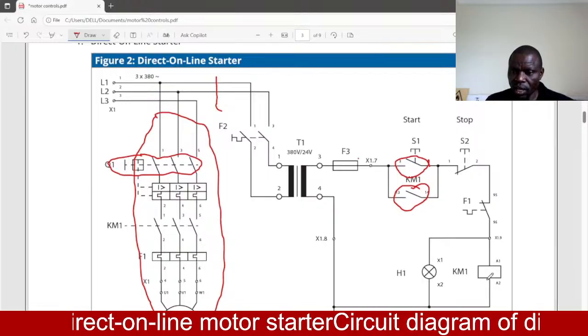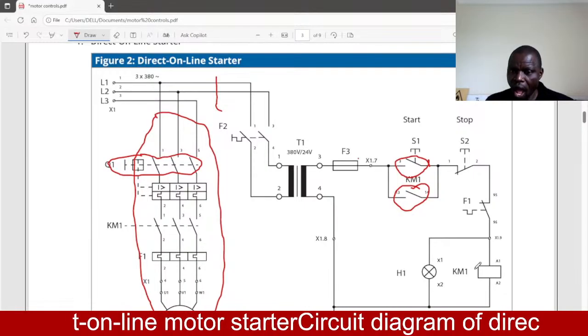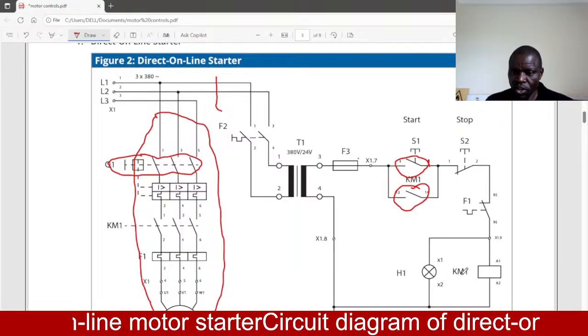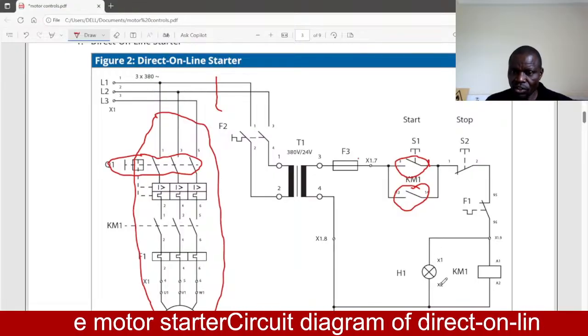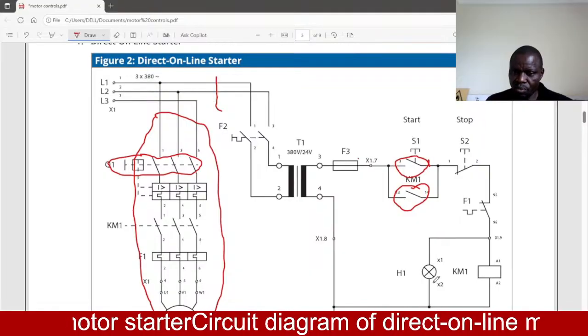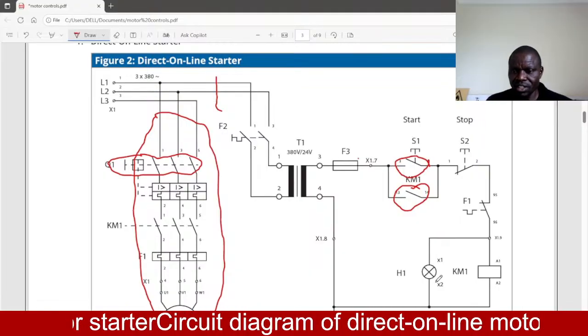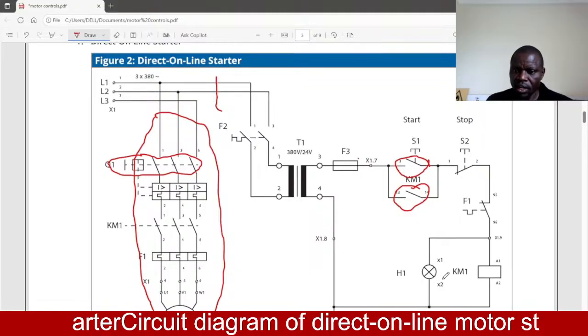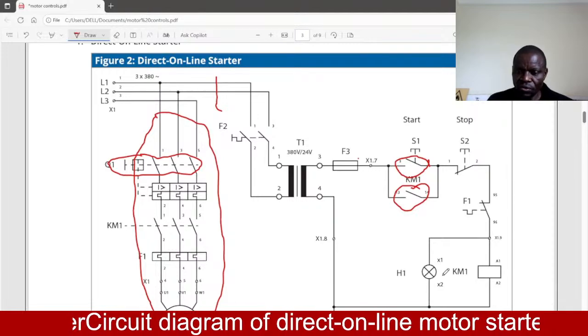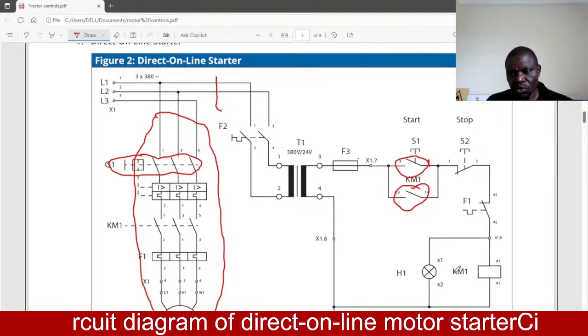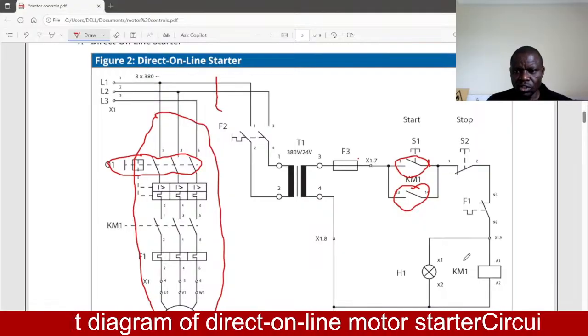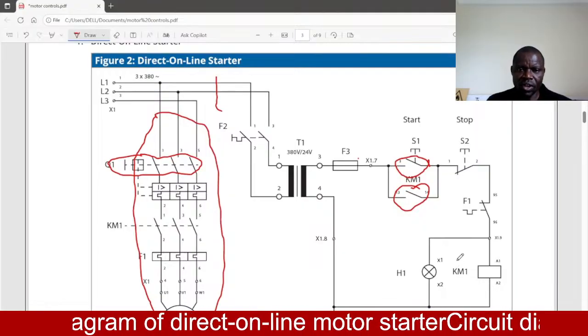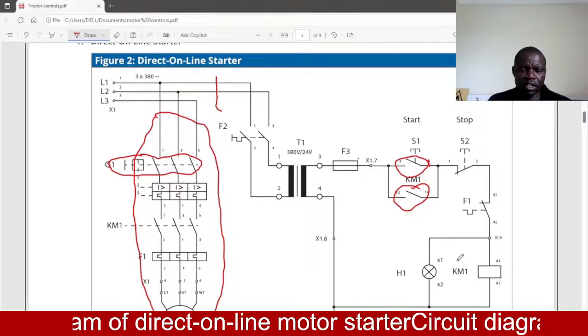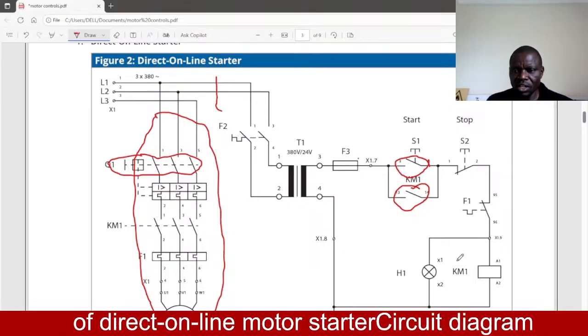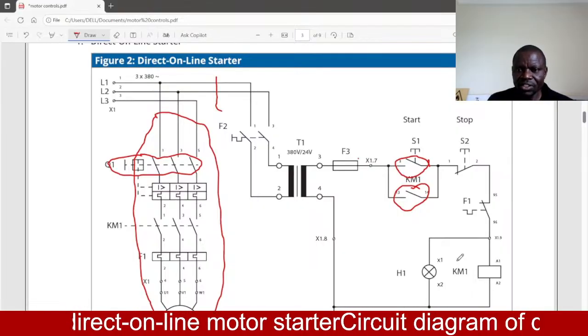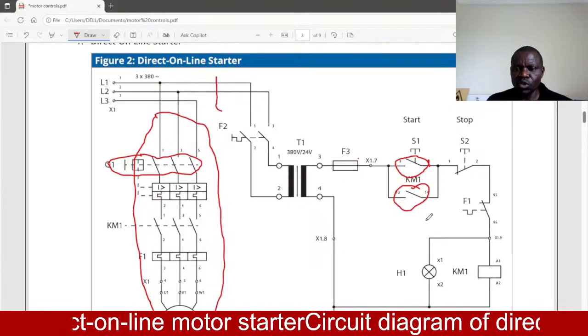This one here, A1, A2, are terminals of the coil, and X1, X2 are terminals of the lamp. The lamp shows that the starter is on, and when the lamp is off, the starter is off. So basically this is what forms a direct online starter. It's a very simple circuit. If you read it, you internalize it, it is very simple to understand.